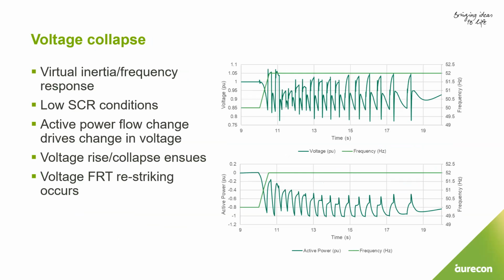Bearing in mind this connection point has an SCR of around 2, what we've done here—no fault is happening, it's just a frequency event. Because of virtual inertia, if frequency goes up, you want to take active power down, and with a battery you have the means to do that. What's happening is that active and reactive power are not decoupled anymore, they're fully coupled. By moving active power, because frequency changes, this causes voltage collapse and triggers LVRT on the grid forming inverter, with no fault actually happening. You can see this is clearly an unacceptable response.